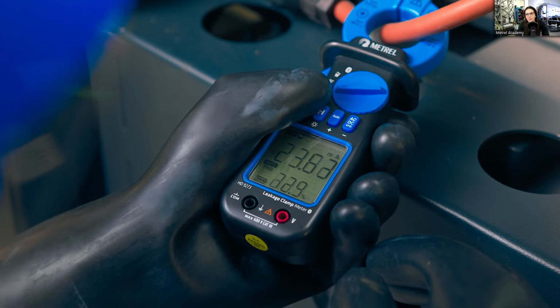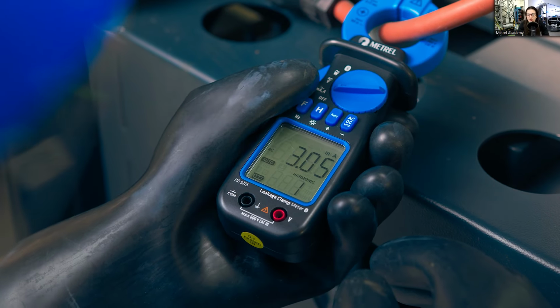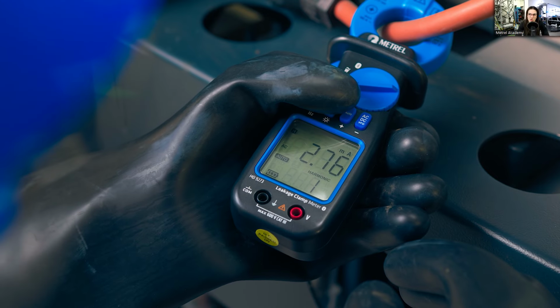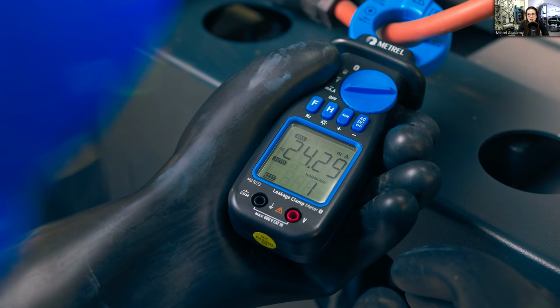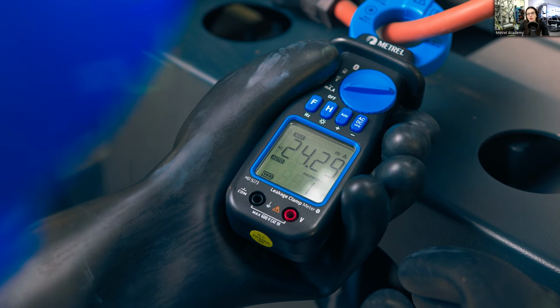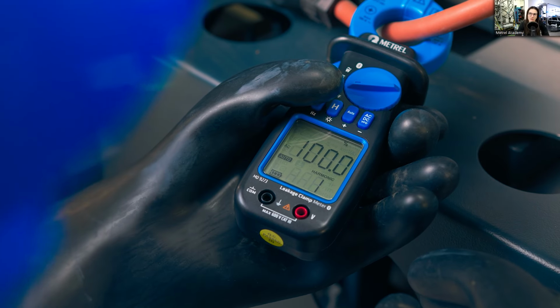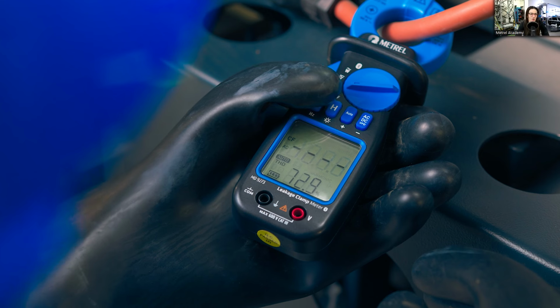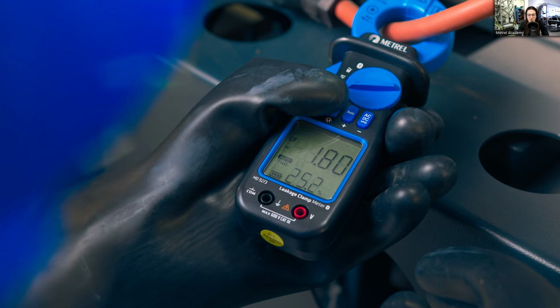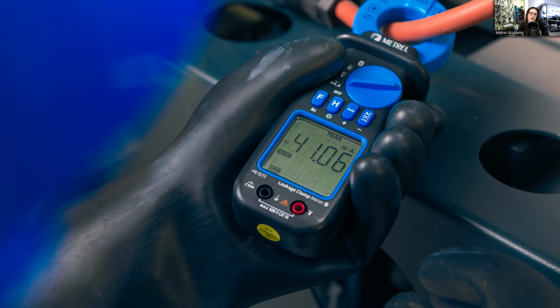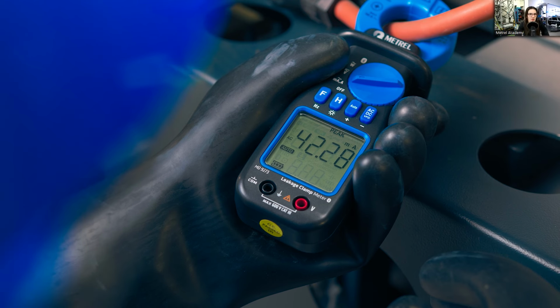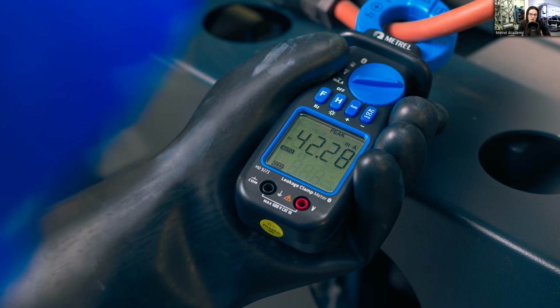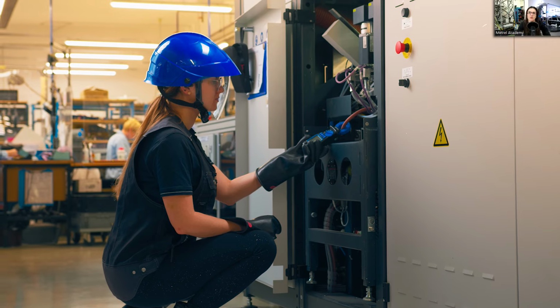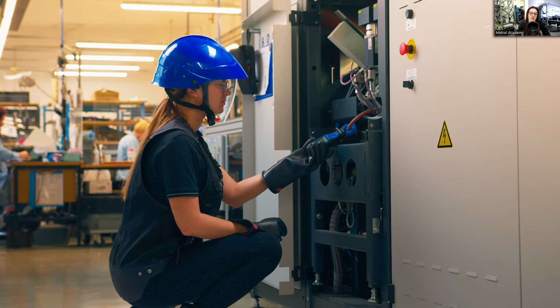I'm going to use filtering to the first harmonic to only watch how the supply frequency is leaking. And I'm going to use recording to the maximum value so that I know which is the highest peak of the leakage current that is happening. This measurement is part of regular maintenance, and we are basically checking how much the heater is leaking during normal operation or in different operation modes.